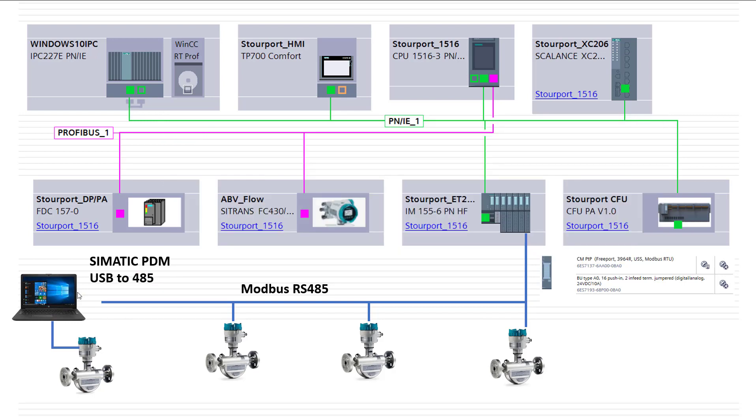Of course, we want to also try and get connectivity to our IoT apps and having PDM maintenance station installed centrally—so you could, for instance, put it on this industrial PC here—would make sense. But the ET200SP doesn't support the Modbus pass-through for PDM.